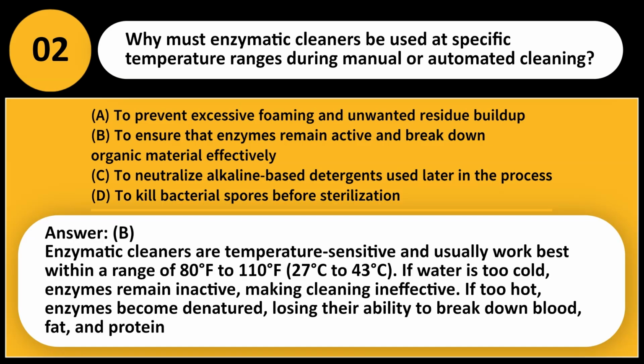Answer, B. Enzymatic cleaners are temperature-sensitive and usually work best within a range of 80 degrees Fahrenheit to 110 degrees Fahrenheit, 27 degrees Celsius to 43 degrees Celsius. If water is too cold, enzymes remain inactive, making cleaning ineffective. If too hot, enzymes become denatured, losing their ability to break down blood, fat, and proteins on instruments.